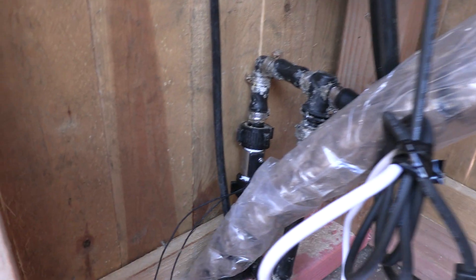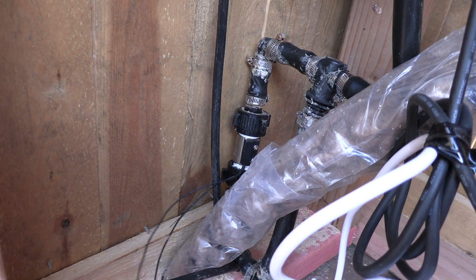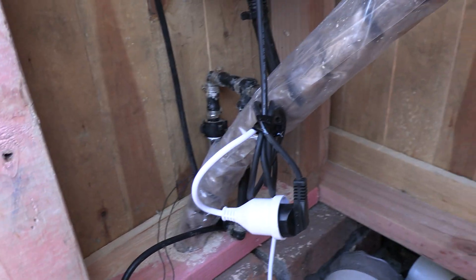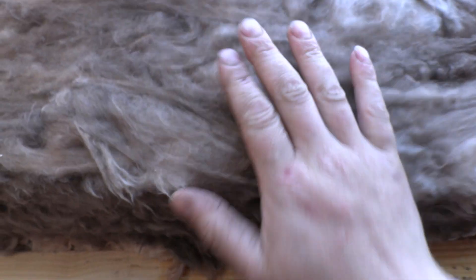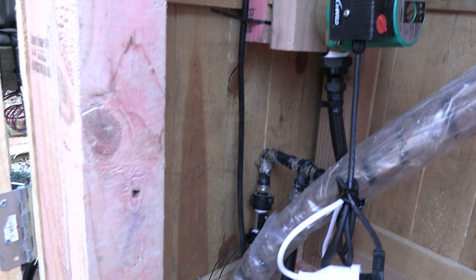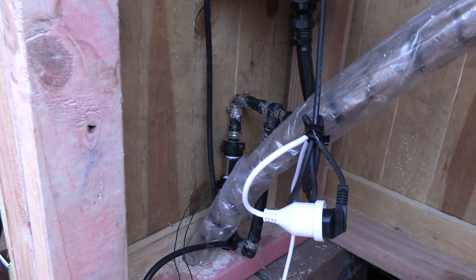So the pump's currently flowing. That's just protection from a blockage — I don't want the pump running dry. On top of this there are also two probes inside the tank — level probes — so that when the water drops below the probes the system will also turn off, in case there's a leakage in the system.